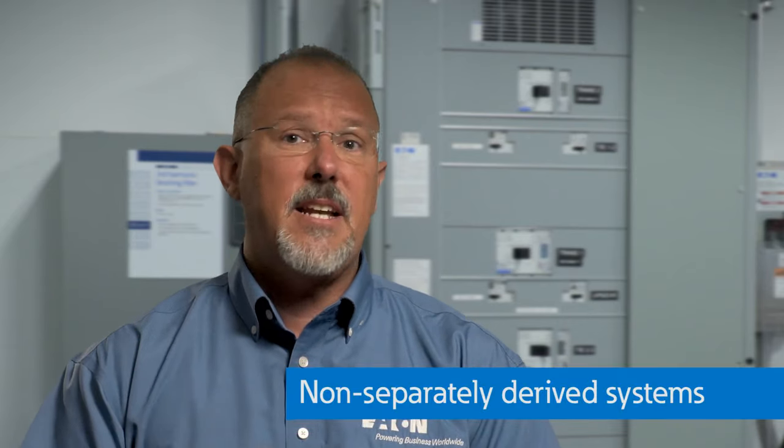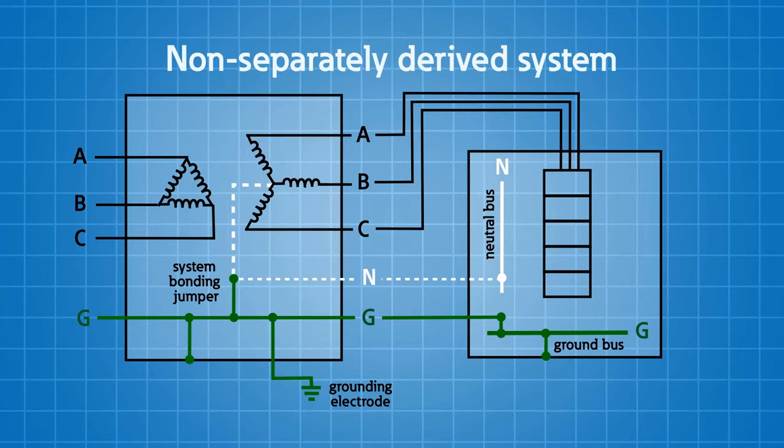Now we've established what a separately derived system is, and depending on how you bond things in the generator — whether you establish a separately derived system — that will drive the solutions you purchase and install. A non-separately derived system: good examples are your downstream panelboards, or a generator that doesn't have an established neutral-ground bond, where you're using a three-wire or three-pole transfer switch. In those cases you keep your grounded conductor separate from your equipment grounding conductors in all of those locations.